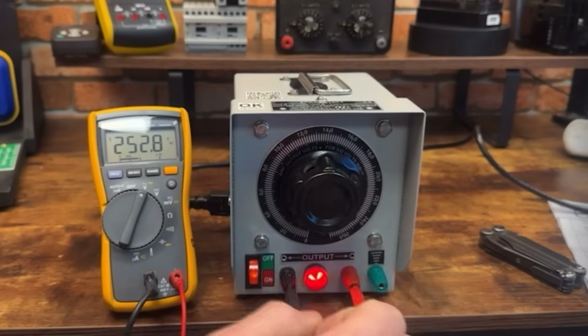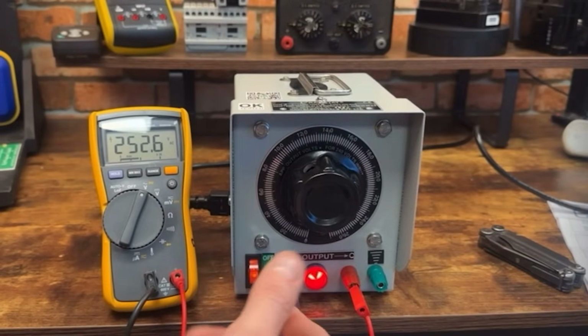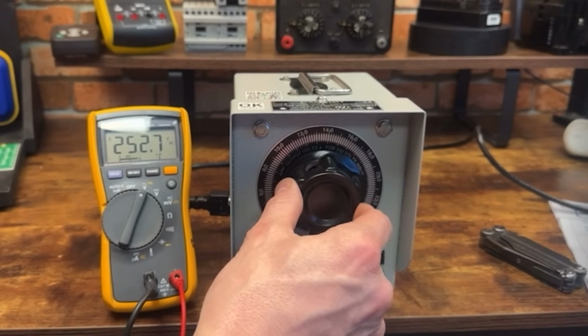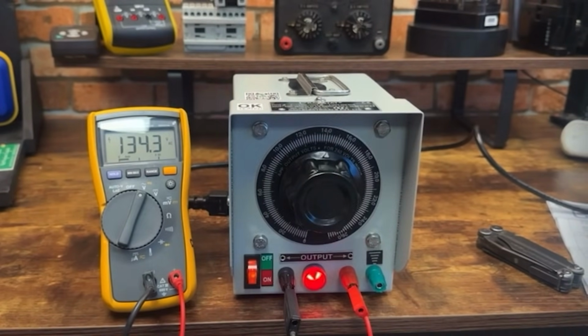For example, if I was to plug an EV charger in here, not on load because obviously it won't power that - it's only got 2 amps - but if I was to then plug it in now and just crank it up a bit, it should cut off. Voltage sensing relay should cut off. If I drop it down to 140 volts like that, it should cut off. So there you go, that's the VARIAC.